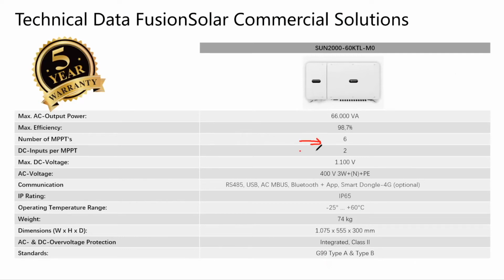6 MPPTs, 12 strings per inverter, maximum input voltage 1100 volts per MPPT, output 400 volts. It's IP65, weighs 74 kilograms, and has integrated AC and DC surge protectors. All our inverters have these features, so all of them have surge protectors, and they are compatible with the requirements from the UK.